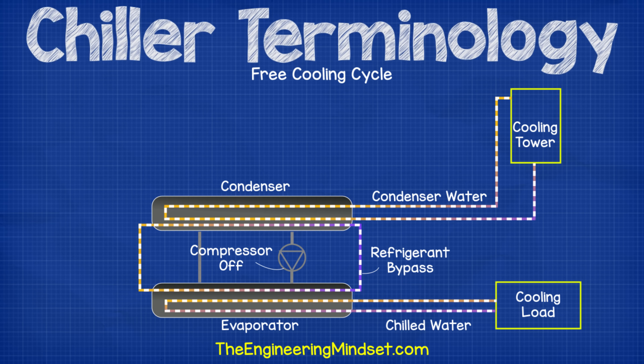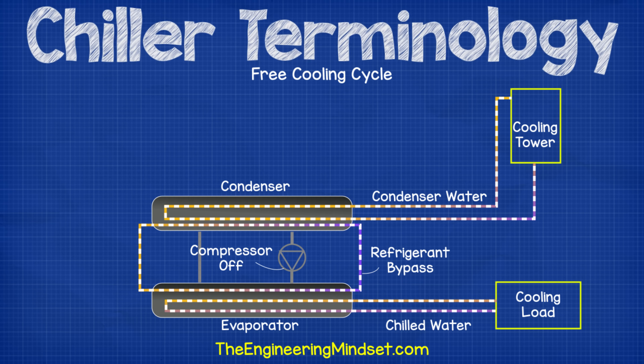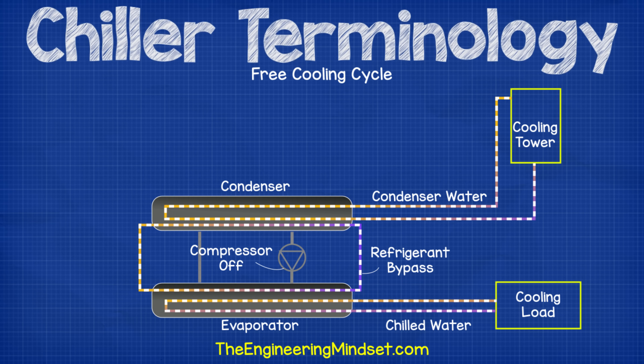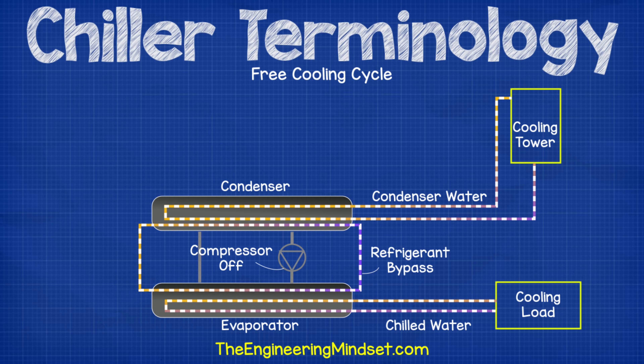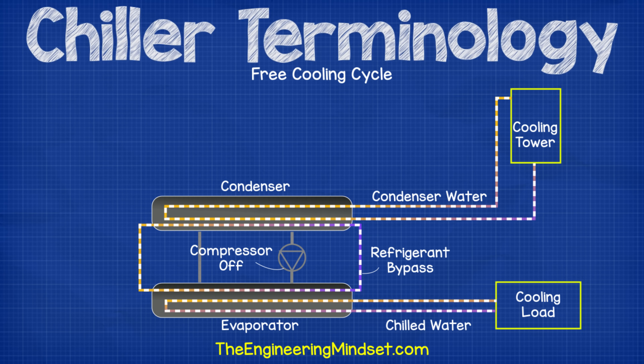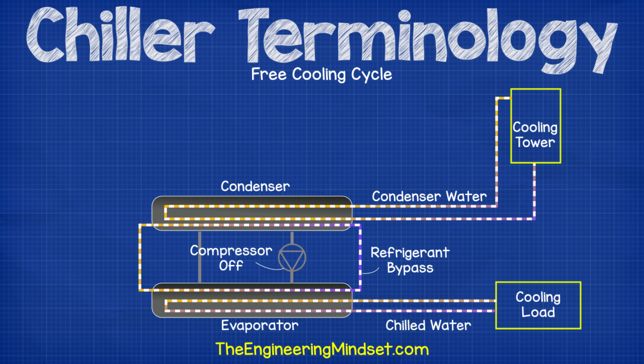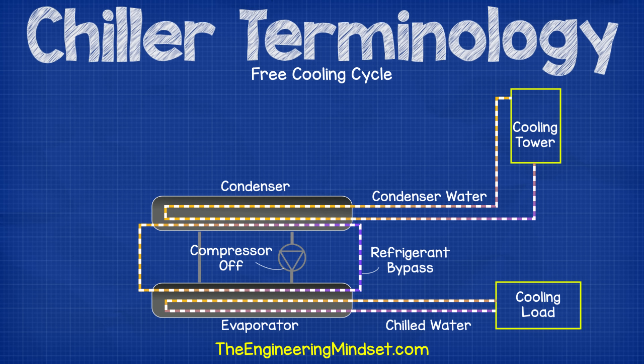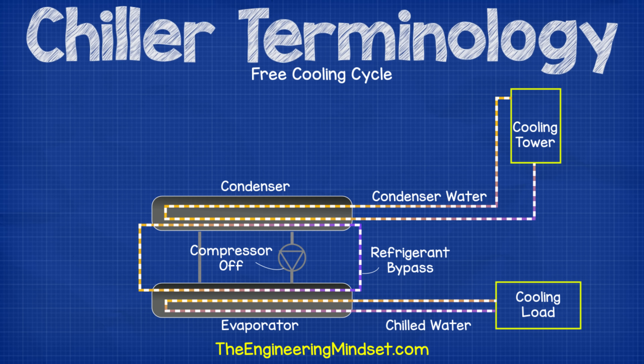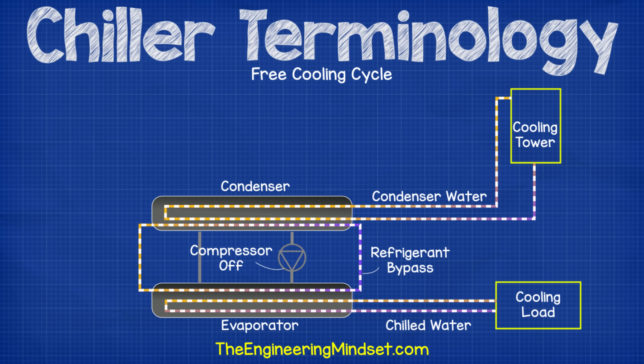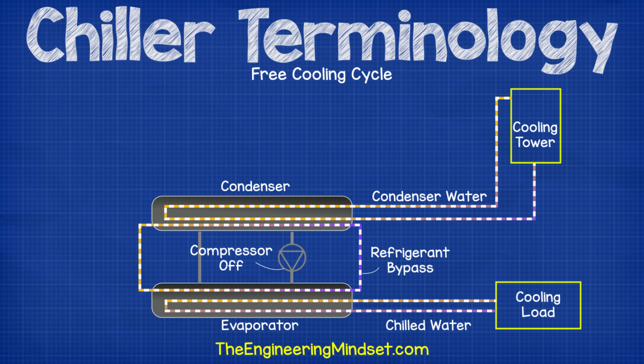Free cooling. This refers to a cooling control strategy which rejects heat without, or with minimal use of, the compressor. This strategy can only be used in certain ambient conditions — it can be enabled when the outdoor air temperature is below the set point temperature. Some chillers have this function built in, others can be retrofitted, or the system can be modified to accommodate this.